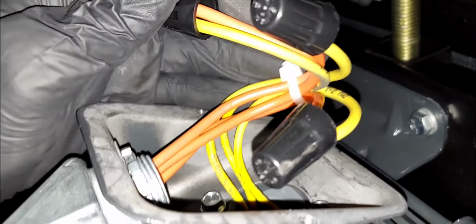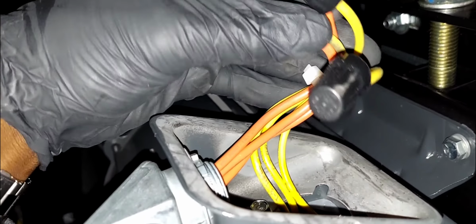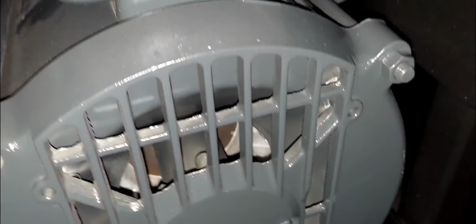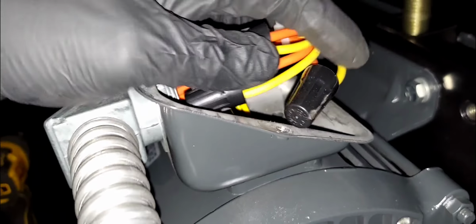I think I'm going to have to take my meter out because this motor does not have any overload whatsoever. This is just 3-phase. There's no safeties in here. Low voltage. This is line voltage. Yeah, it's getting very interesting, guys. So stay tuned. I'm gonna grab my meter and start checking the wires as they leave, the schematics, where they go, and see where I'm losing my power.